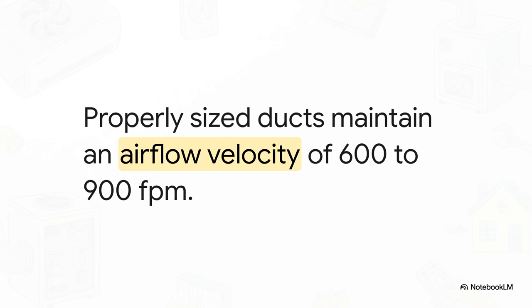Proper duct design isn't just about moving air around, it is all about speed. Ducts must maintain an airflow velocity of 600 to 900 feet per minute. If the ducts are too small, the friction literally kills the airflow. If they are too large, the air velocity completely drops off and the system basically can't breathe at all.